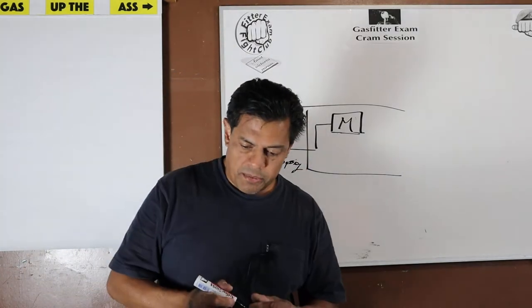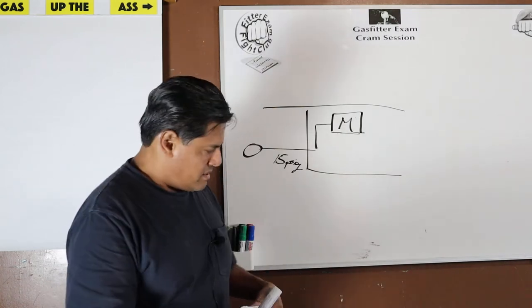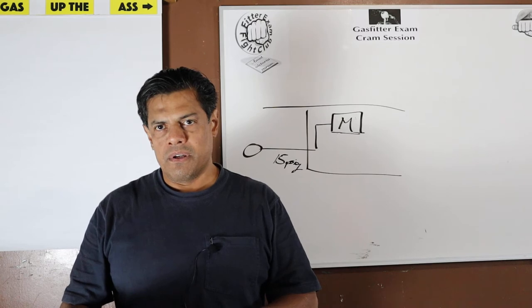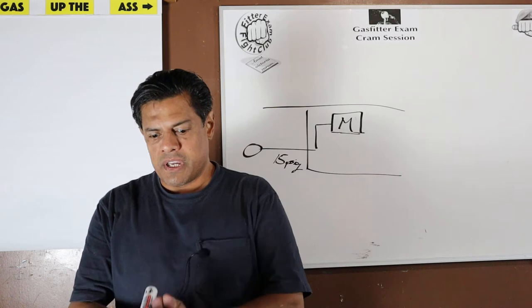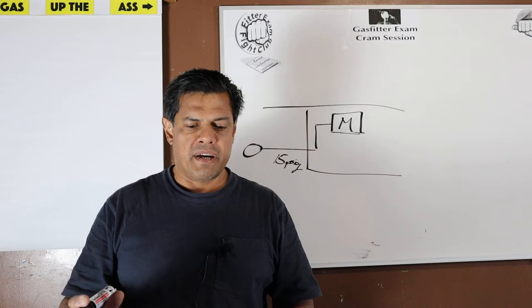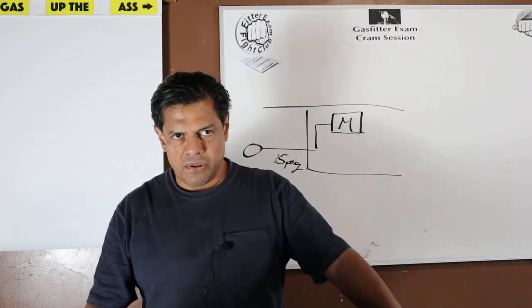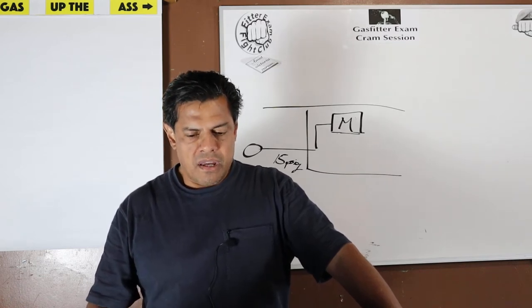In fact, now's a good time to point something out, because this is another question. You're going to get it. No way around it. High pressure gas is 15 psi or greater. You hit 15 psi, you've got high pressure gas. I make this distinction because this is very fine wording. It's a matter of semantics, how something can mean different things just because you phrase it a little differently.